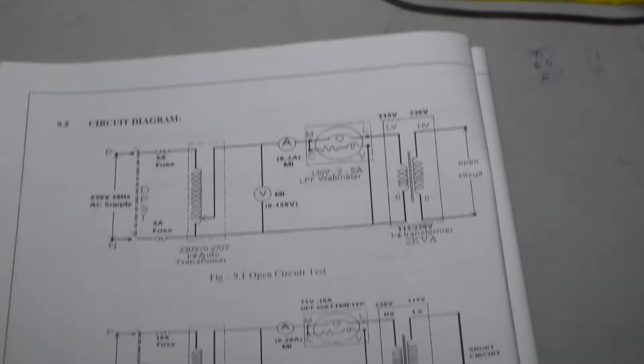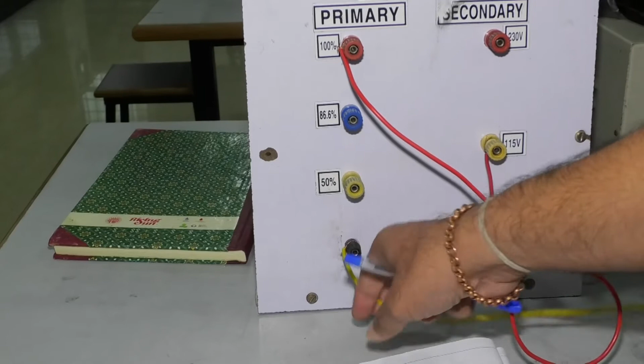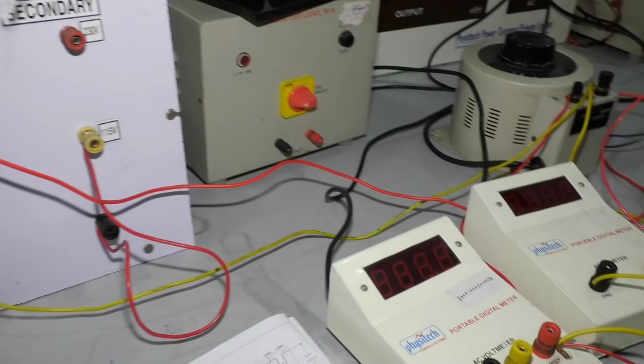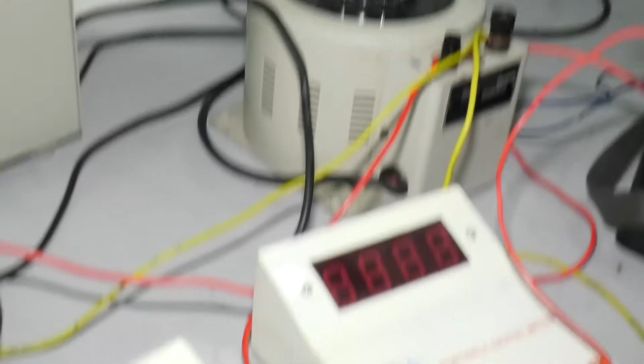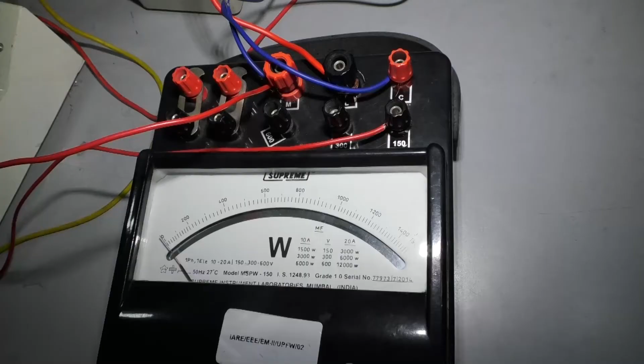You can observe the short circuit connection here. We have short circuited the phase and neutral, and we have given connection to the 230 volts and neutral. Again, from this variac we have connected it to the voltmeter as in the circuit diagram, and the ammeter and the wattmeter. We will use the UPF wattmeter instead of the LPF wattmeter, because in the short circuit the current will be high, so we will replace this wattmeter with the UPF one.